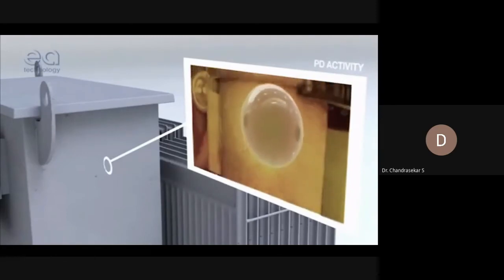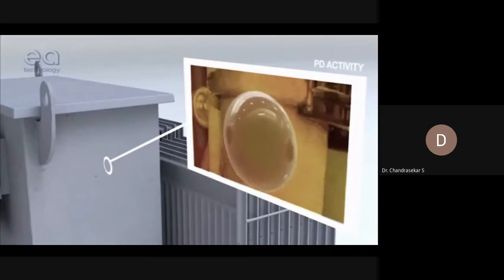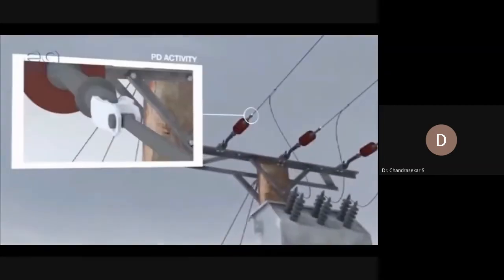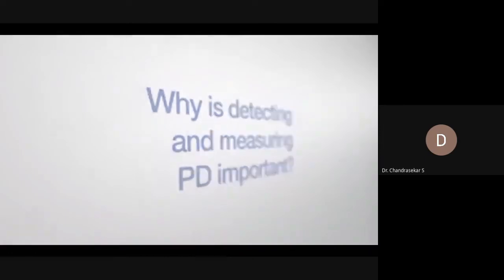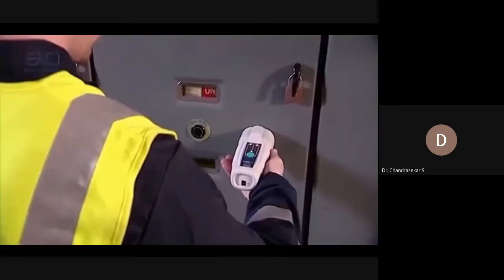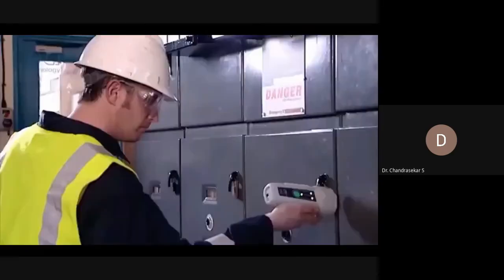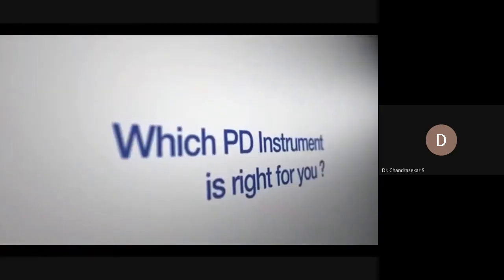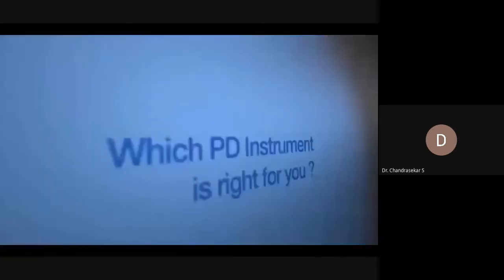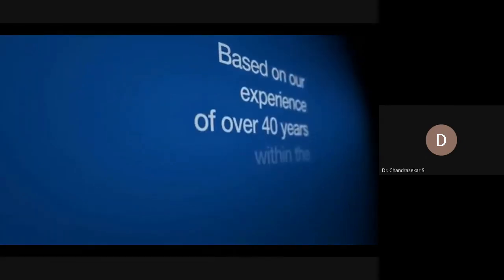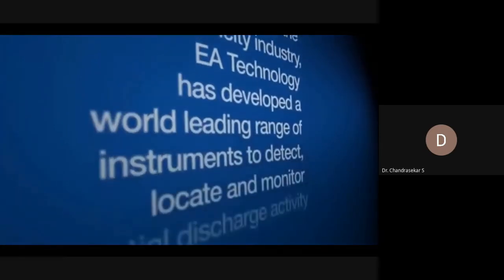This can occur in the voids within solid insulation, across the surface of insulating material, within gas bubbles in liquid insulation, or around electrodes in gas, or it can produce corona. Partial discharge is the most reliable indicator of the true condition of insulation within live assets. Therefore, being able to detect, locate, and measure partial discharge on an ongoing basis is critical to managing your assets as efficiently and reliably as possible. Based on our experience of over 40 years working within the electricity industry, EA Technology has developed a world-leading range of instruments to detect, locate, and monitor partial discharge activity.